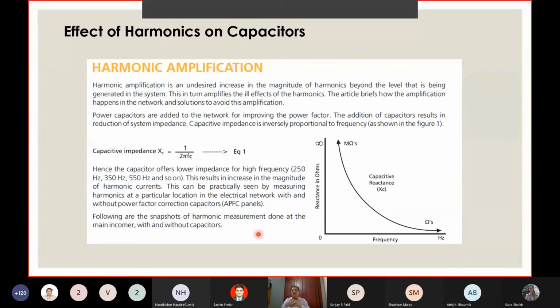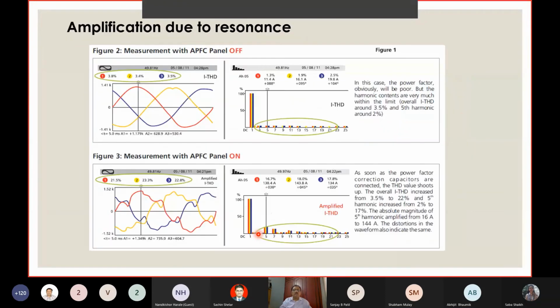If it finds another low impedance path, like a capacitor, it will flow through the capacitor, causing one, damage to the capacitor elements, two, the capacitor will amplify because of the effects. So what we recommend, as you can see here, whenever we make an audit, we switch off the capacitor and make measurements, and then we switch on the capacitors and make measurements to understand what is the distortion in waveform, as you can see here, and also the amplification of harmonics.